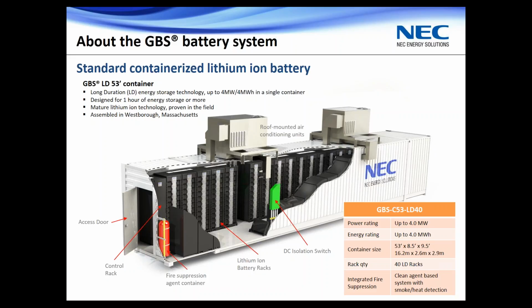It's comprised of lithium-ion battery racks, which you can see lined up here. This cutaway shows only one row of racks; there's actually another row on the other side of the container, so there are two rows total. We can fit up to 4 megawatts and 4 megawatt hours in a single container. However, for this case, we've configured it as a 2 megawatt, 3.9 megawatt hour energy storage system.